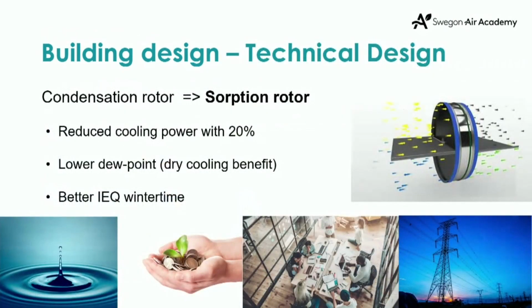Good. I guess also inside the air handling unit you had some special selection. Yes, we changed from a normal condensation rotor to a sorption rotor. By doing that, we could reduce the size of the reversible heat pump a lot, so we could go down in size. By that, we didn't only save money, we also saved the environment, because we have a lower carbon footprint and less refrigerants, which is great. And the sorption rotor is also beneficial during wintertime because we take the moisture from the building and get it back into the building again, improving the indoor environmental quality in winter when you'd otherwise get dry air indoors.